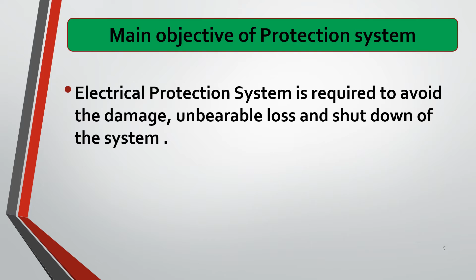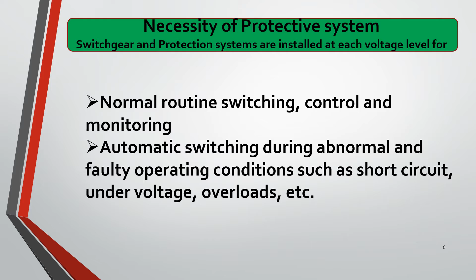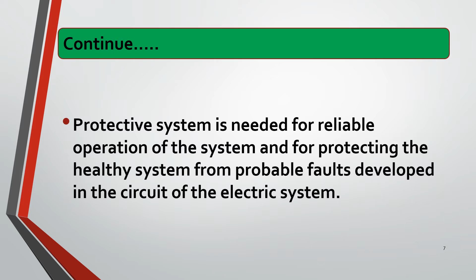As shown in the previous diagram, right from generation up to utilization, there are a number of stages: generation, transmission, distribution, utilization, and these all things are taking place at different voltage levels. So switchgear and protection systems are installed at each voltage level for normal routine switching, control and monitoring, and for automatic switching during abnormal and faulty operating conditions such as short circuit, under voltage, overload, etc. So protective system is needed for reliable operation of the system and for protecting the healthy system from probable faults developed in the circuit of the electric system.